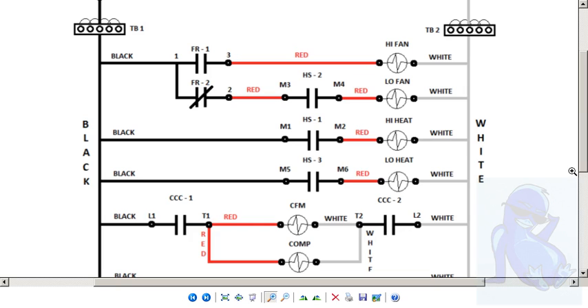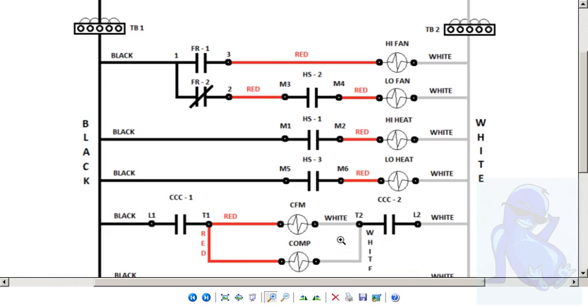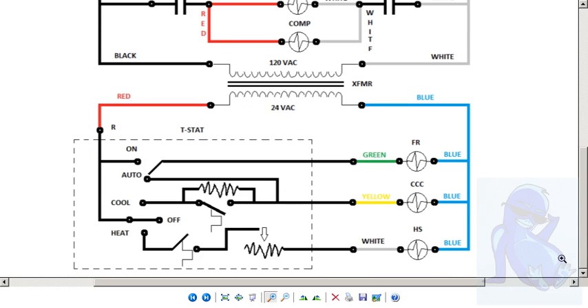It would turn on and off without doing that, but in this case it's a contactor with 2 legs that opens and closes. The compressor is shown there too. It's wired in parallel, and it goes back to that same leg and closes out. That completes the high voltage side.